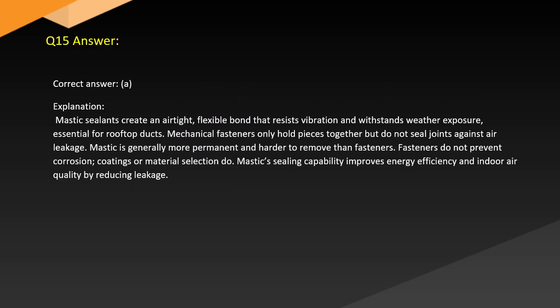Answer. Correct answer: A. Explanation. Mastic sealants create an airtight, flexible bond that resists vibration and withstands weather exposure, essential for rooftop ducts. Mechanical fasteners only hold pieces together but do not seal joints against air leakage. Mastic is generally more permanent and harder to remove than fasteners. Fasteners do not prevent corrosion; the coatings or material selection do. Mastic sealing capability improves energy and indoor air quality by reducing leakage.